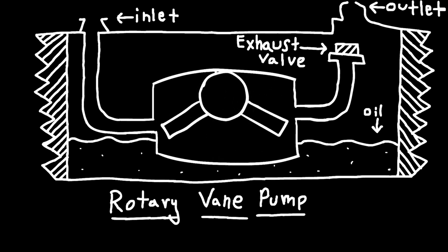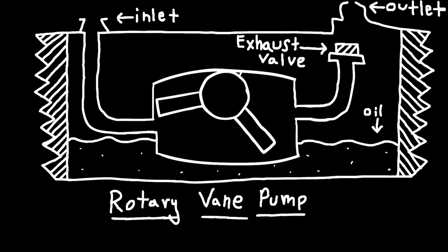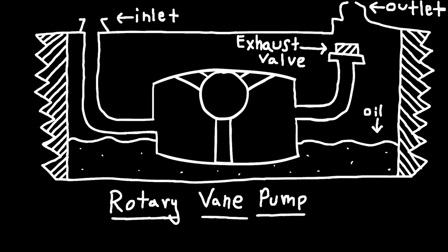One small drawback you can imagine to rotary vane pumps is that when the motor stops and the vane stops spinning, gas can flow back through the rotary vane pump and suck all of the oil into the vacuum chamber. To prevent this, a one-way anti-suckback valve is normally used in the roughing line.